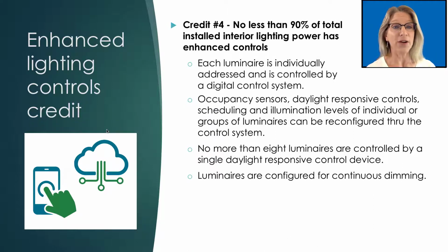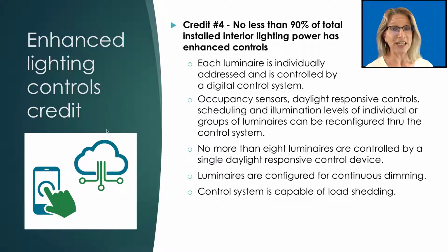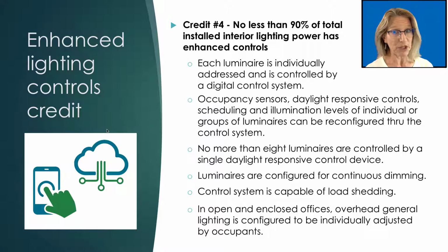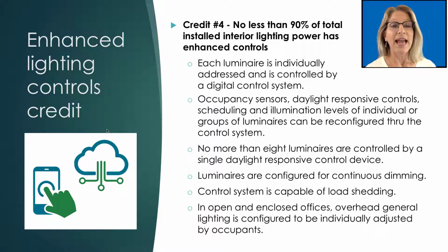And the luminaires are required to be configured for continuous dimming. The control system needs to be capable of load shedding. And then specifically for open and enclosed offices, overhead general lighting needs to be configured to be individually addressed by the occupants. So now recall that occupant sensor controls are now required in open office areas. The capability for the occupant to adjust the lighting in their portion of an open office area is yet another expansion of lighting control within this space type.